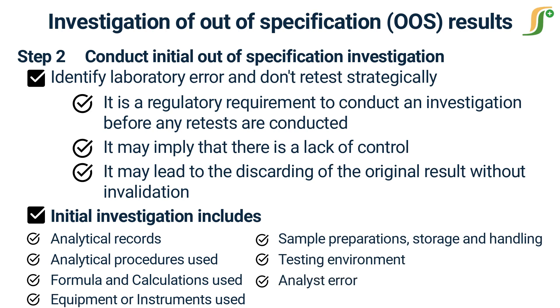If some of the initial investigational areas look like the assignable causes in step 1, that's correct — the objective of an initial investigation is to ascertain if an assignable cause is readily apparent which might be attributed to the out-of-specification result. In that case, when an assignable cause is found without a doubt, declare the original out-of-specification result as invalid and repeat the test to replace the invalidated result.